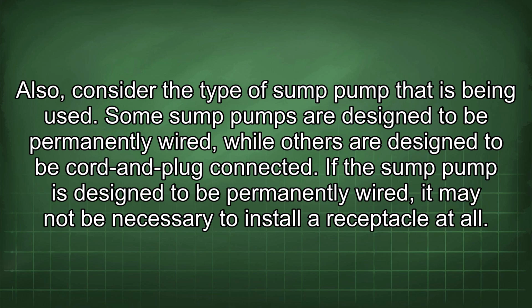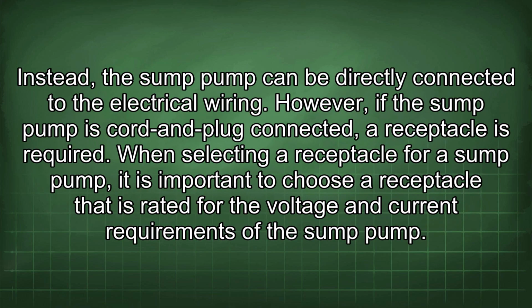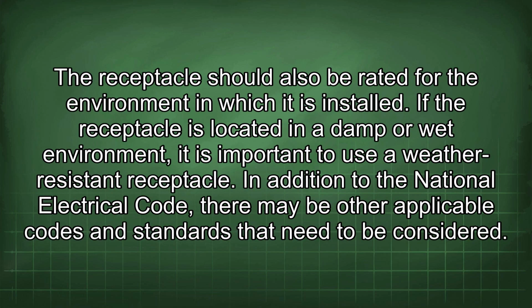Some sump pumps are designed to be permanently wired, while others are designed to be cord and plug connected. If the sump pump is designed to be permanently wired, it may not be necessary to install a receptacle at all. Instead, the sump pump can be directly connected to the electrical wiring. However, if the sump pump is cord and plug connected, a receptacle is required. When selecting a receptacle for a sump pump, it is important to choose a receptacle that is rated for the voltage and current requirements of the sump pump. The receptacle should also be rated for the environment in which it is installed. If the receptacle is located in a damp or wet environment, it is important to use a weather-resistant receptacle.